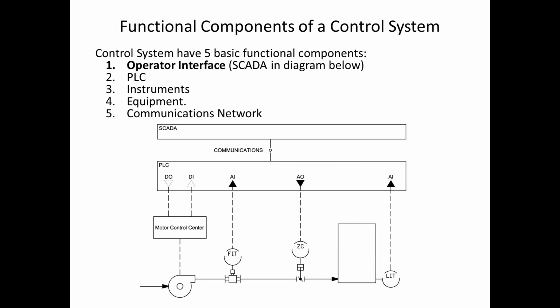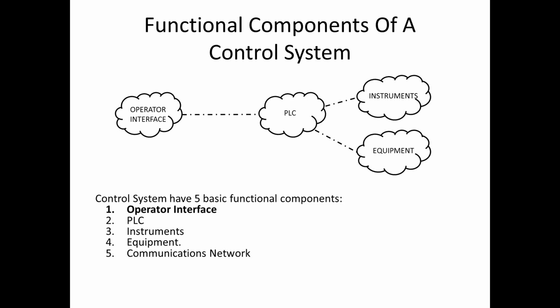And the operator interface, let me go back a slide. The operator interface is actually the window into the process. There's little control that goes on in the operator interface, as it doesn't usually have any smarts in it, but it allows an operator to take a look at the process, and if the operator needs to, it can give instructions to the PLC, and the PLC will pass those instructions along to a piece of equipment.